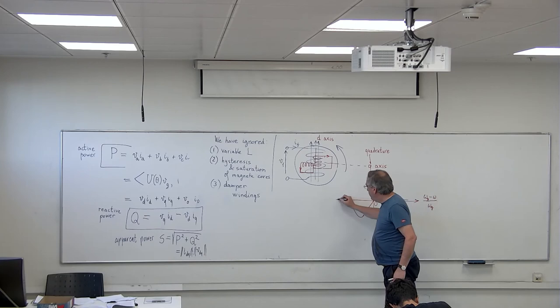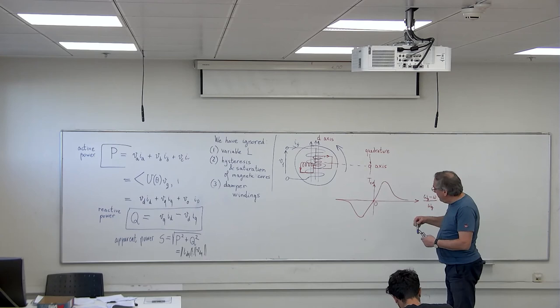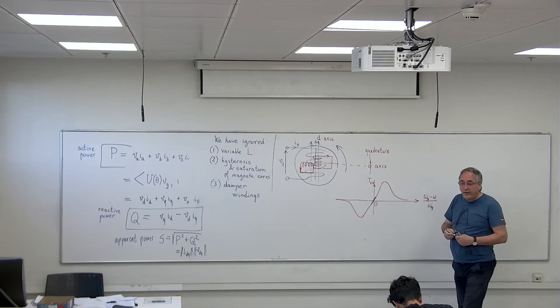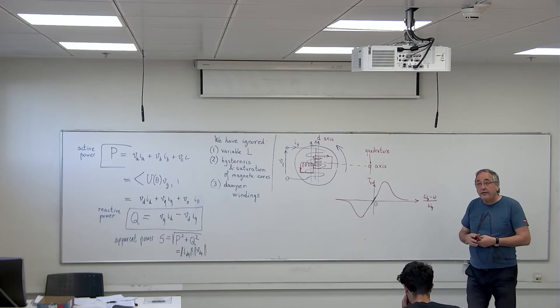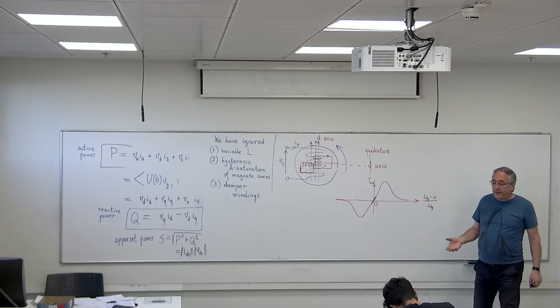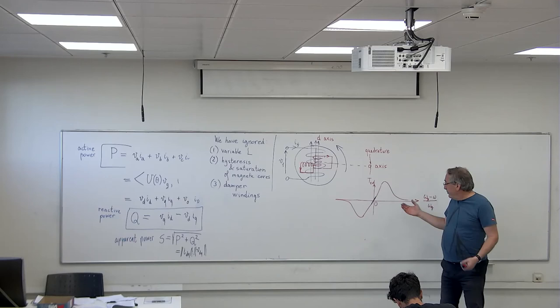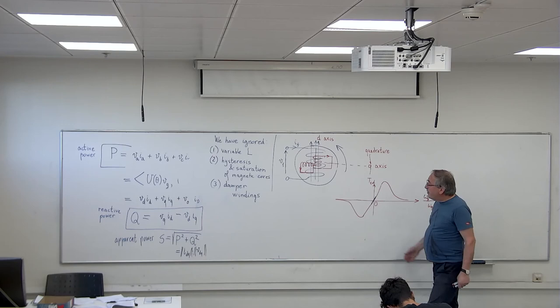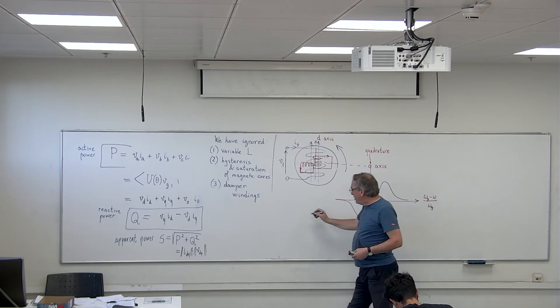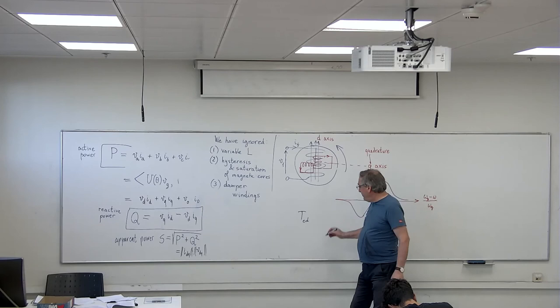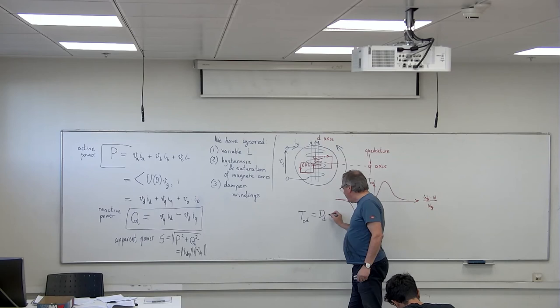Now, we are only interested in this very narrow region around zero, because the slip in the case of a synchronous generator will be very small. The local frequency will be very close to the grid frequency. So we are here in this linear region. And in this linear region, you see that there is an electric torque proportional to the deviation of the frequency from the grid frequency.